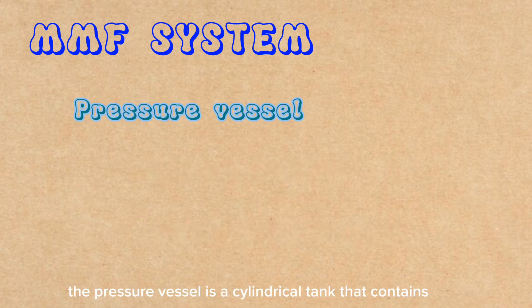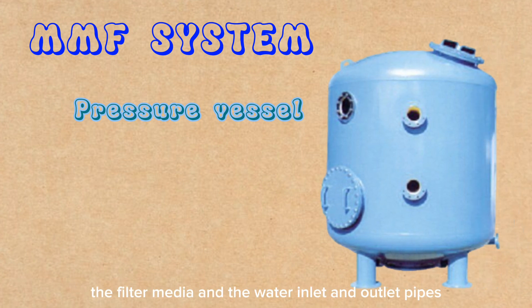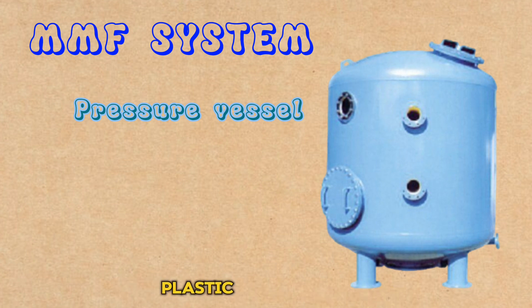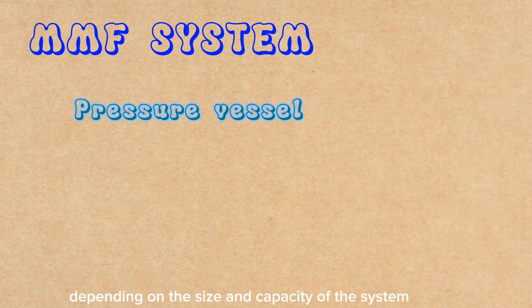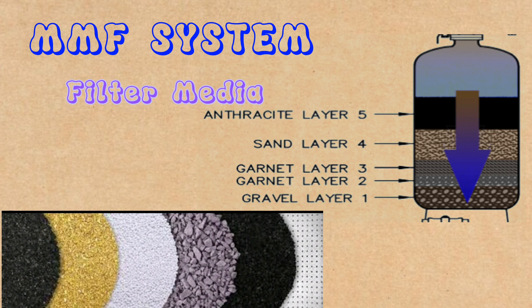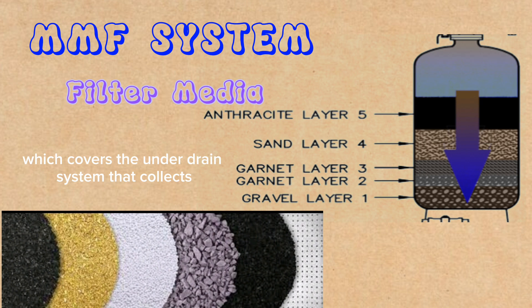The pressure vessel is a cylindrical tank that contains the filter media and the water inlet and outlet pipes. The pressure vessel can be made of steel, fiberglass, or plastic, depending on the size and capacity of the system. The filter media is a layer of different materials that have different sizes and densities, usually composed of three layers: anthracite, sand, and garnet. Anthracite is the lightest and coarsest material, sand is the medium-weight and medium-sized material, and garnet is the heaviest and finest material. The filter media is supported by a layer of gravel at the bottom of the pressure vessel, which covers the under-drain system that collects the filtered water.